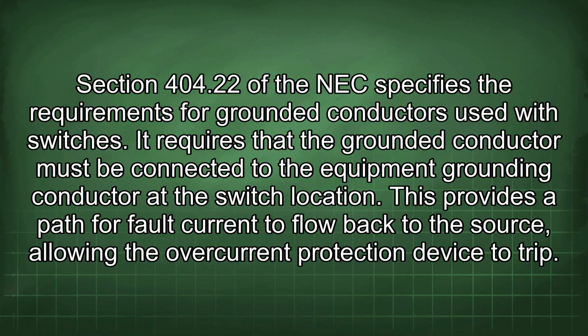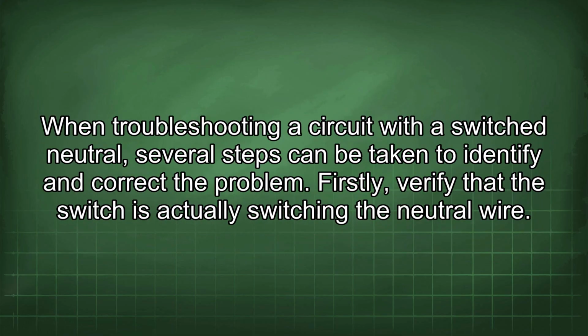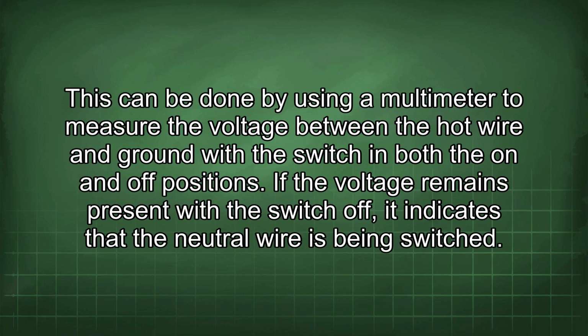This provides a path for fault current to flow back to the source, allowing the overcurrent protection device to trip. When troubleshooting a circuit with a switched neutral, several steps can be taken to identify and correct the problem. Firstly, verify that the switch is actually switching the neutral wire. This can be done by using a multimeter to measure the voltage between the hot wire and ground with the switch in both the on and off positions. If the voltage remains present with the switch off, it indicates that the neutral wire is being switched.